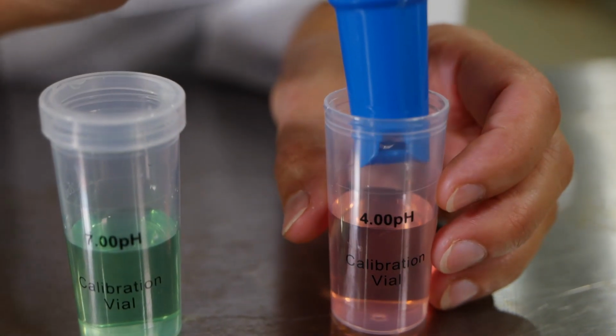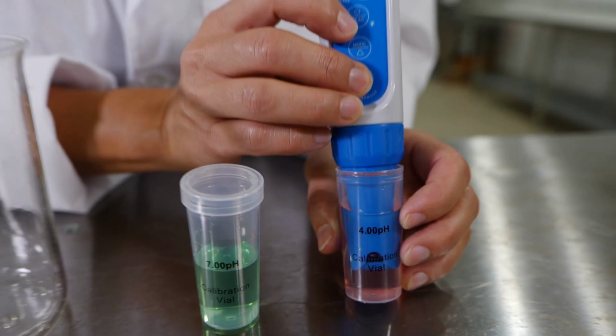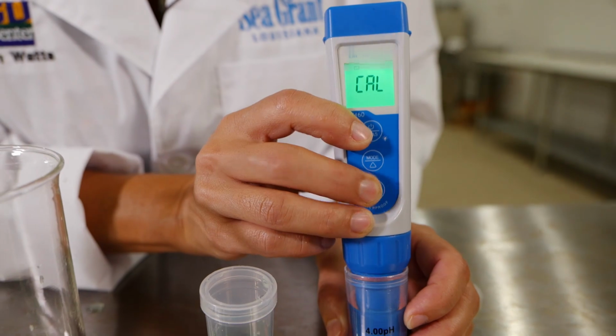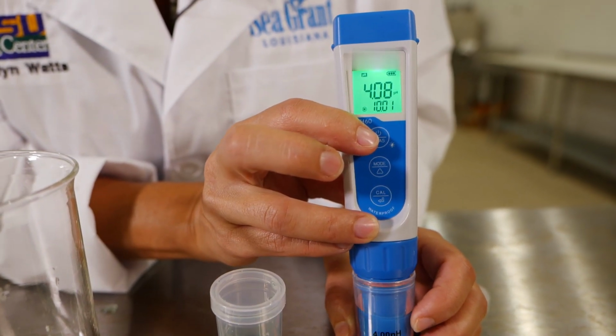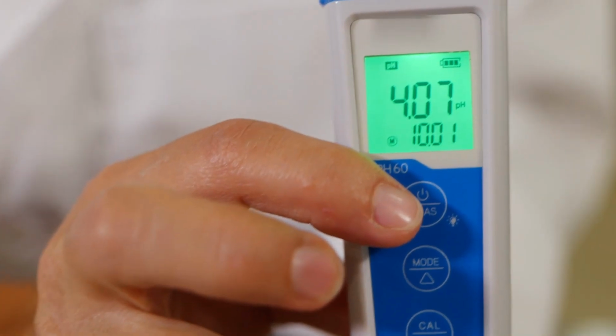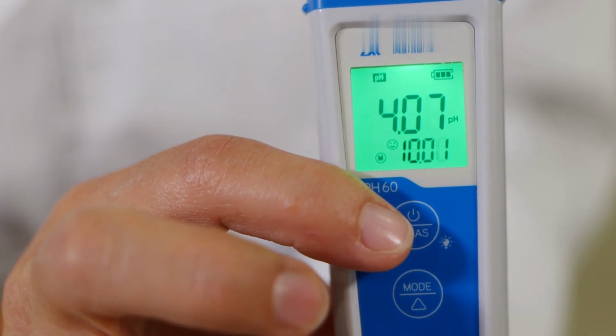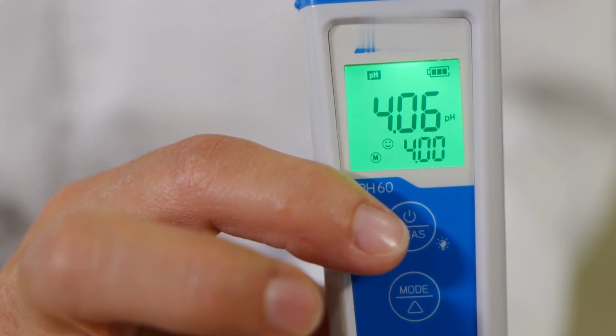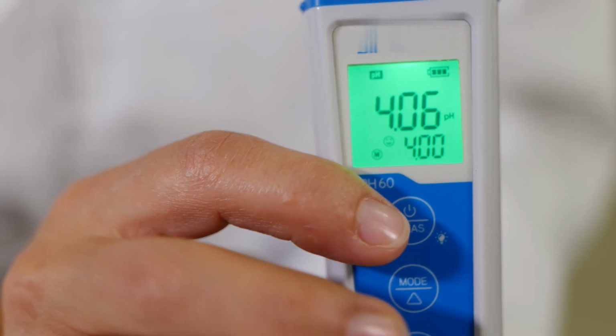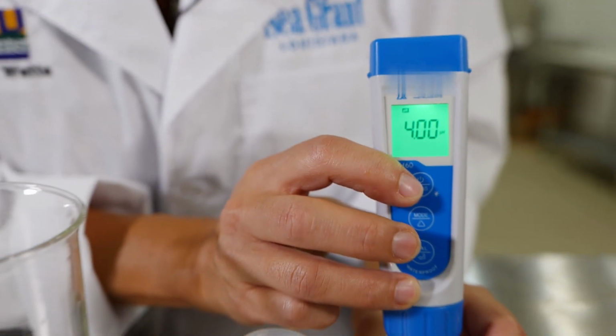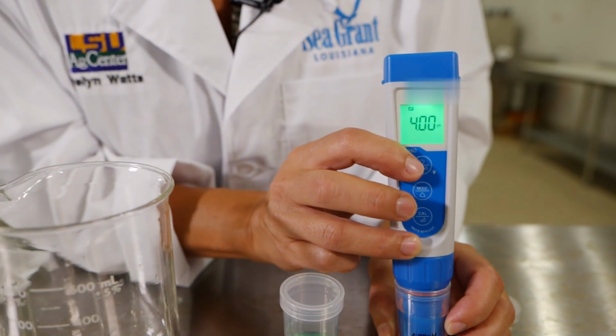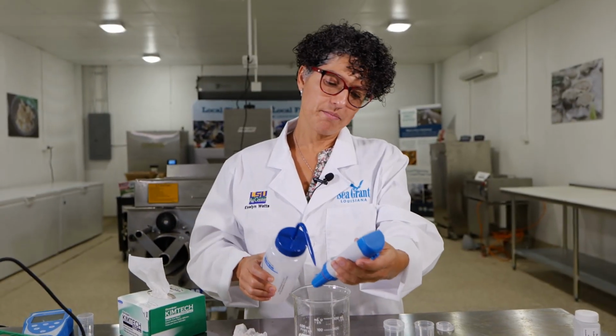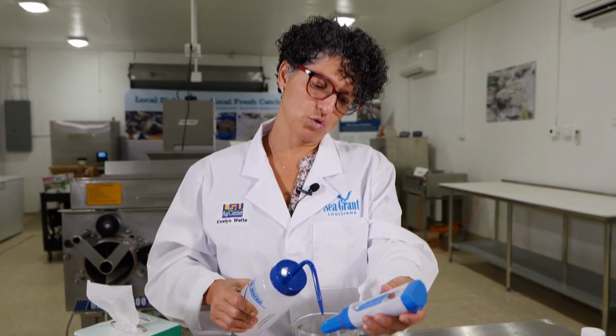Again, we're going to immerse the probe, hold the calibration button, and let the pH meter again detect the buffer. And once it's ready, it's going to show us the smiley face again. We press the calibration button, and we're done. Remember that every time that you use your pH meter, you need to calibrate it, or every time that you get a suspicious reading.